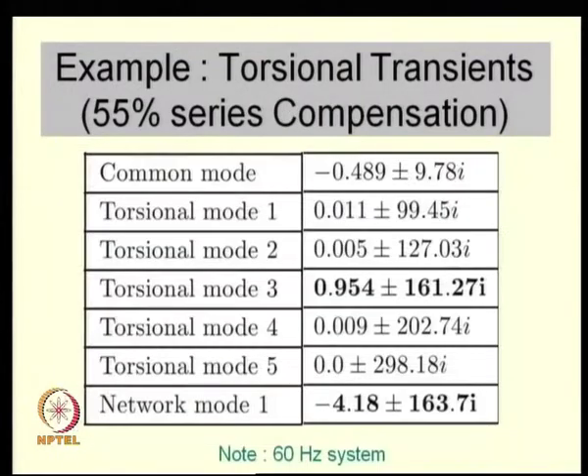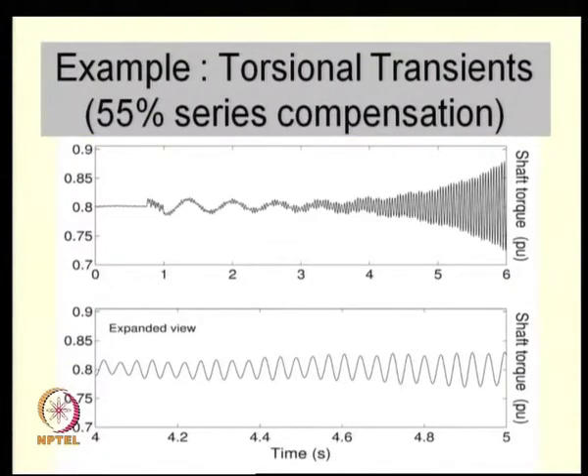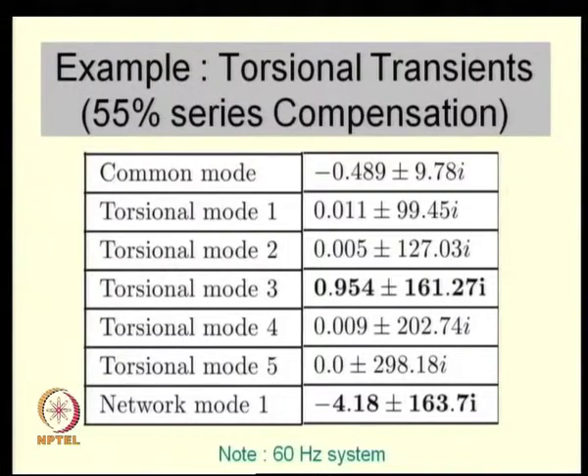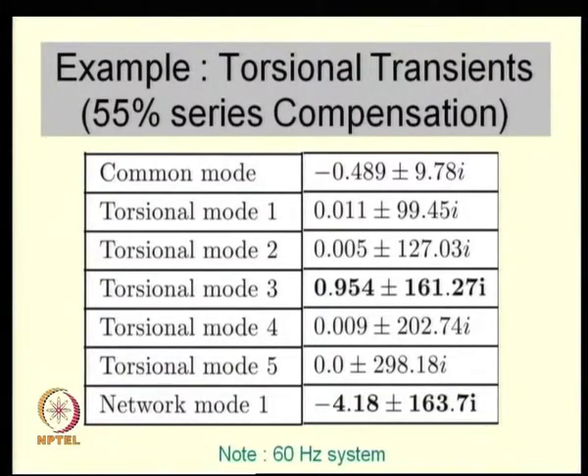Looking at the eigenvalues obtained for this system, we see that torsional mode 3 is very badly affected, which is also confirmed in the simulation study where that particular mode grows with time. In this study, no mechanical viscous damping was considered, so the only damping possible was due to interaction with the electrical network. As a result, all torsional modes appear to have positive real parts.